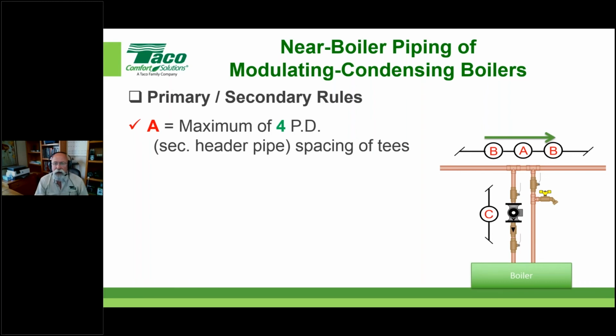We're talking here not inches but pipe diameters, and it's the pipe on the secondary side. In this case, the boiler is coming in and back up into this portion of the system piping. So what size is this secondary piping? Whatever you want, say 1 inch, to make the math easy. Don't exceed 4 pipe diameters, but actually make it shorter than that.